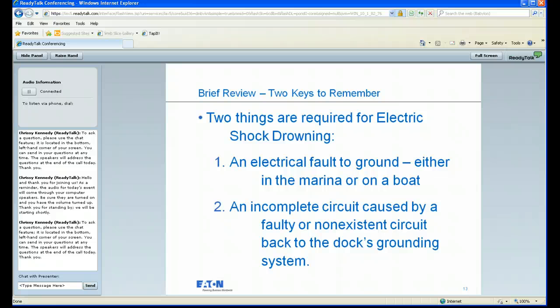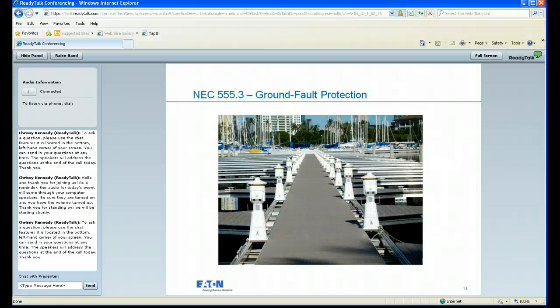As a brief summary, there are two things that are required for an electrical shock drowning. There needs to be an electrical fault to ground, either caused in the marina or on an inadequately wired boat. And there also needs to be an incomplete circuit caused by faulty or non-existing circuits back to the grounding system. There needs to be some sort of an issue or some sort of problem with the grounding system allowing that leakage current to enter the water and potentially become a serious problem.